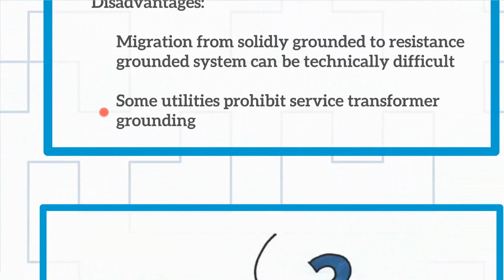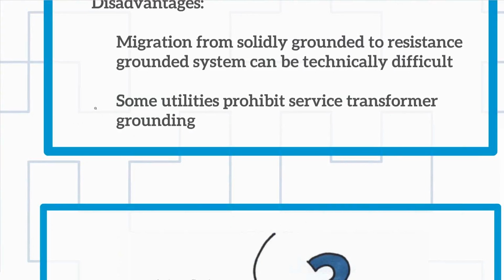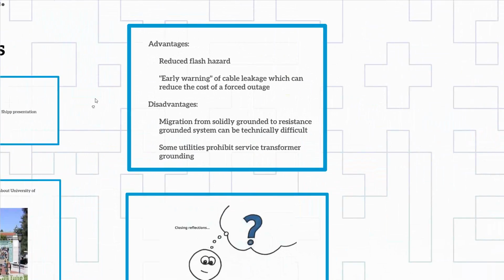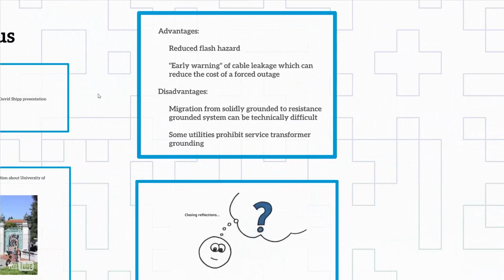And a few times the industrial says, screw you, I'm buying the transformer and buying it at 69 kV and I'll do what I want because you just cost me $10 million in my last outage. Yeah, that's the argument. And they'll understand that argument, especially in campus power systems. You'd probably approach the Public Service Commission for a variance on that. So I'm glad to know the California State Public Service Commission has permitted it. We'll have to go into some research, as I'd like to see in black and white where that allowance is permitted in the state of California.